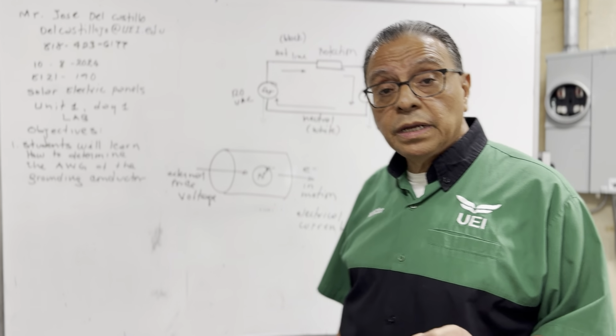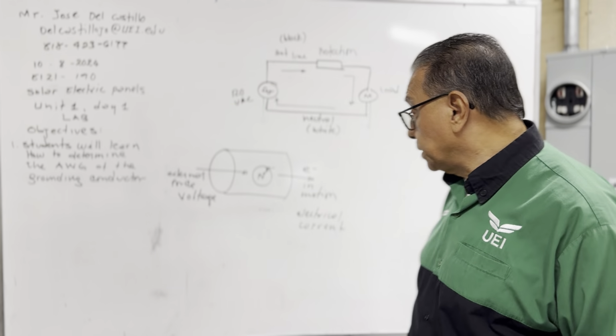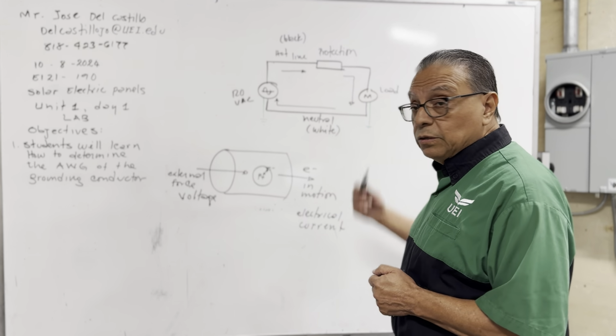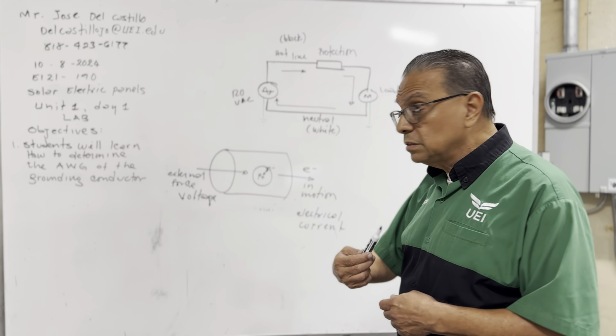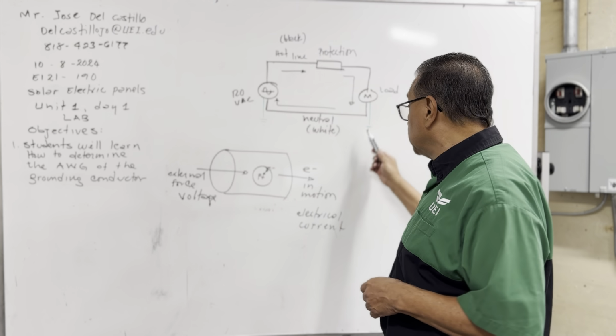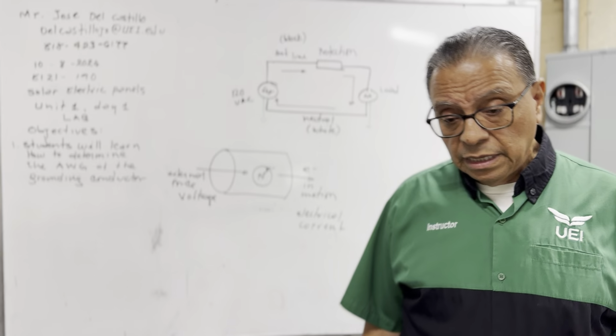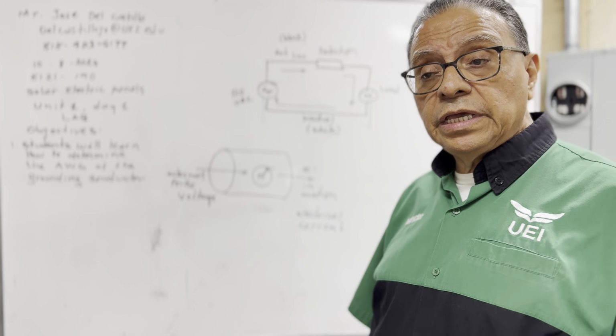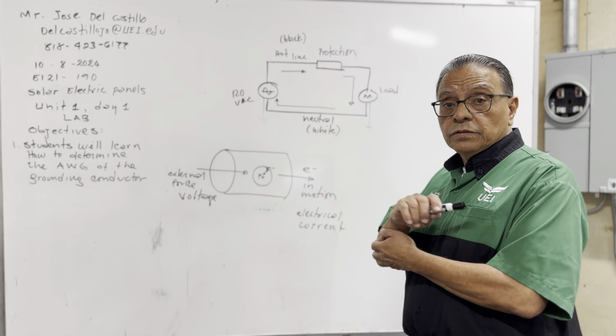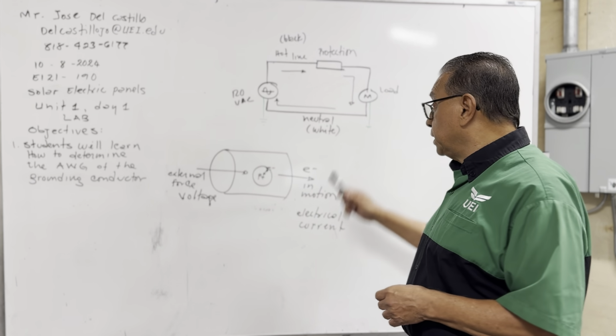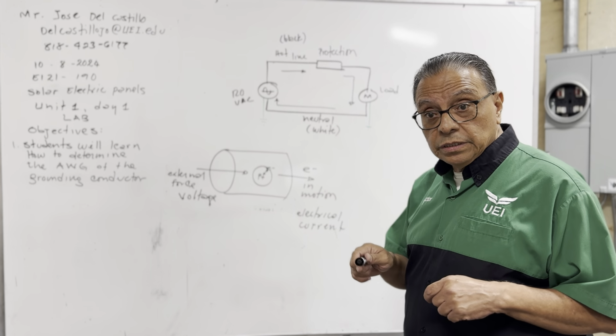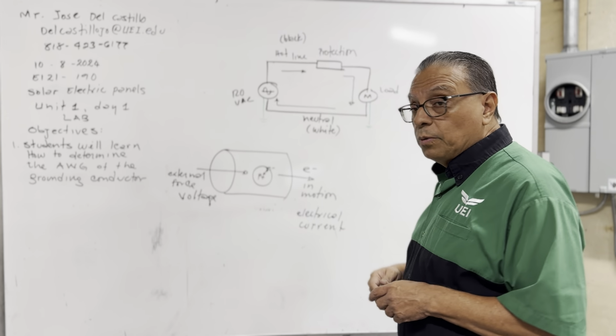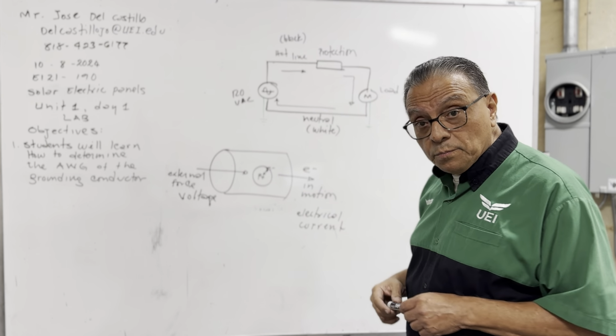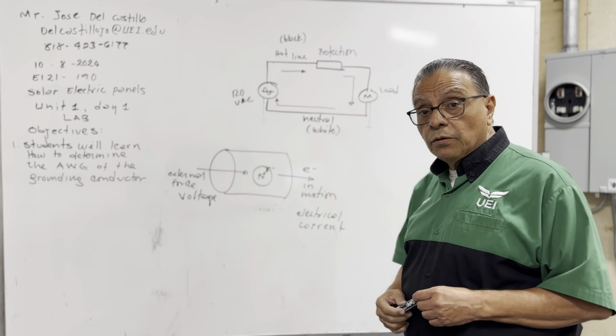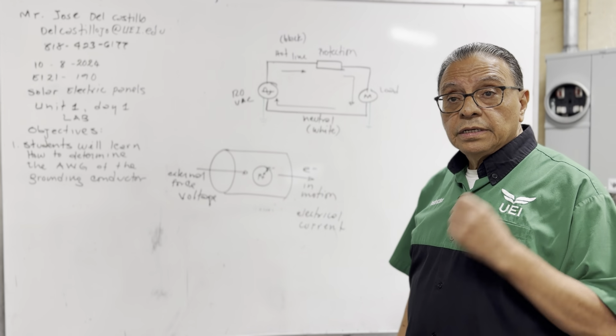And keep in mind, 0.5 ampere could stop a human being's heart. So we need to offer the electrons an alternative way to get back to the source, which is my ground. My ground is the alternative way that the electrical current or electrons will use in case of an open neutral. In that way, the ground will be used to close the circuit, not to continue providing power to the load. No, the ground is used to get back to the source and stop the electrical circuit.